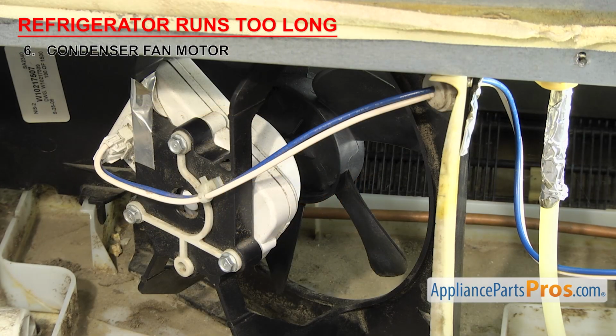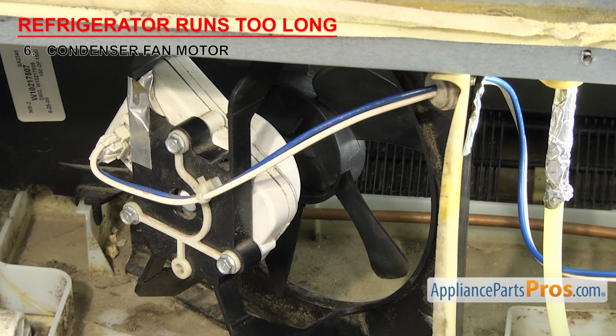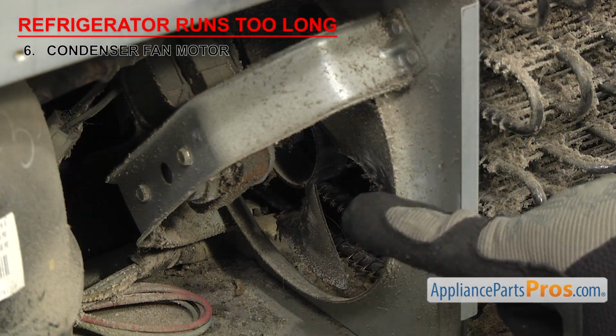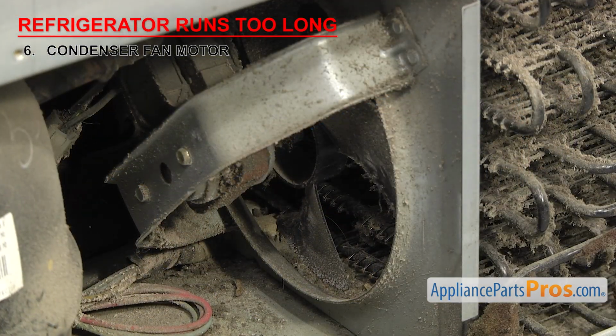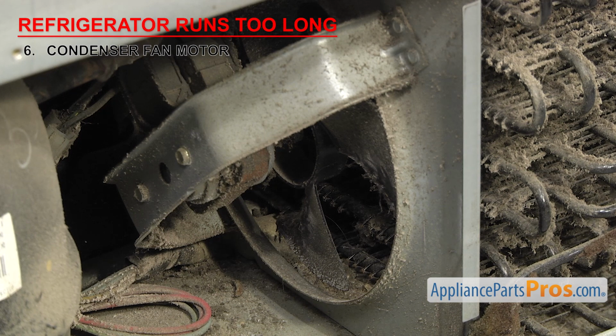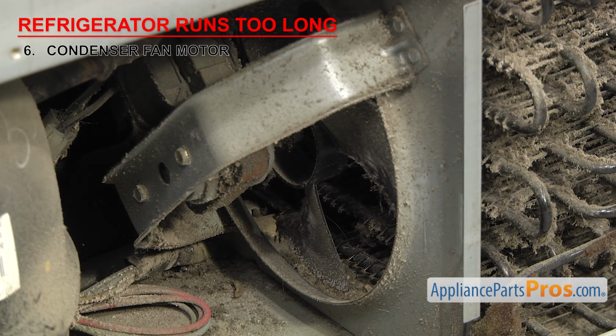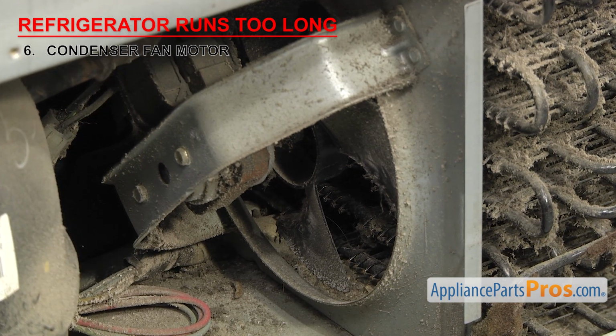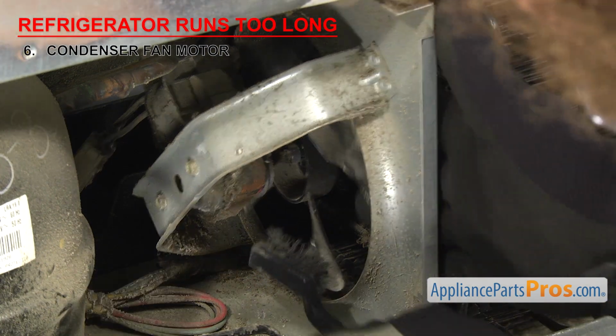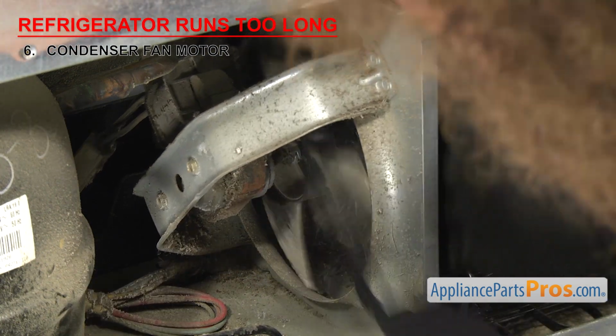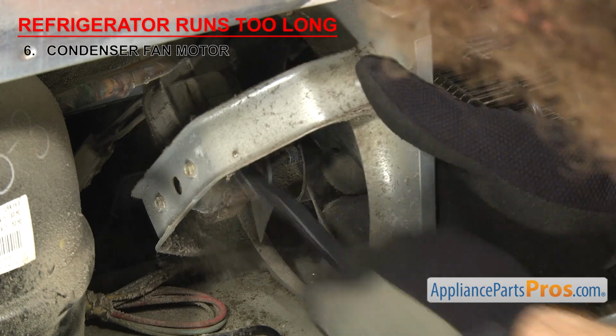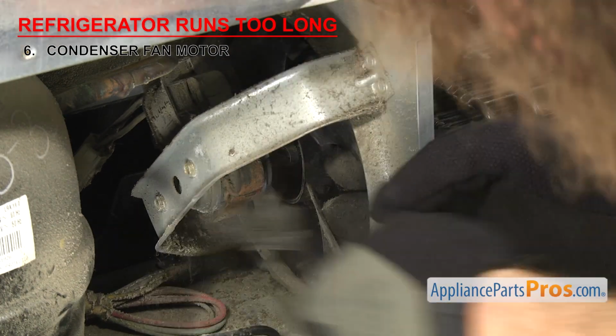Due to its location, the condenser fan motor is exposed to constant heat and dust. If the motor and fan blade are covered in dust, it could be running hot and causing it to run slow, or if it's completely failed, it could cause the compressor and condenser to overheat. If the motor and fan blade are coated in dust, you can try to clean it to see if that helps it run better, but if you determine that the condenser motor has failed, you'll need to replace it.